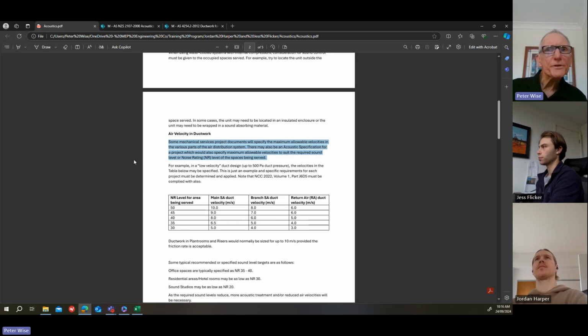No two jobs are the same, as you probably found out already. You've got different consultants, different acoustic consultants if they're involved. They do things in different ways. So you need to find out what documents apply to the project or what's in existence. There may not be an acoustic specification or report. So you just need to look at the mechanical spec. If there's nothing in the mechanical spec, then you need to use your own judgment about what suitable velocities are. But you also need to take note of the NCC because that has requirements on ductwork as well in Part J6D5, which I'll mention in the next paragraph.